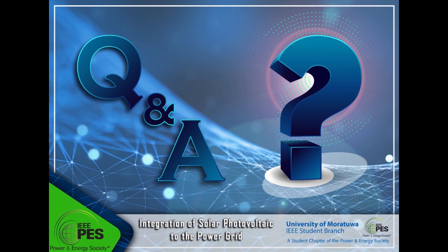Also, if there are other dynamic devices, like another converter connected to a nearby bus in the AC system, you can have interactions between the controllers of the two nearby converters. All these things you can analyze using eigenvalue techniques, and you can avoid those situations by tuning the gains of the controllers to eliminate, or even if you can't eliminate, you can make those oscillations well damped, so that when a disturbance excites this mode, it will be damped out very quickly.